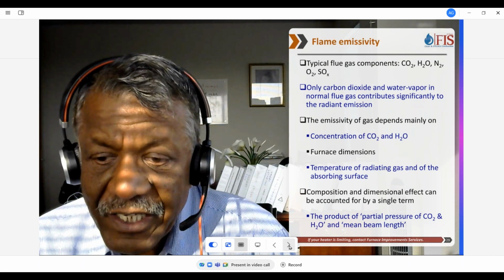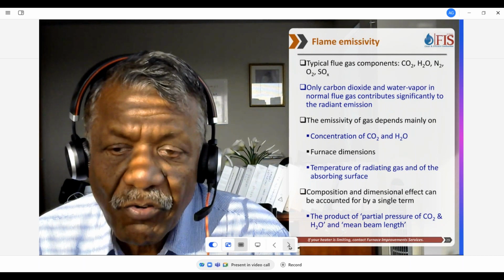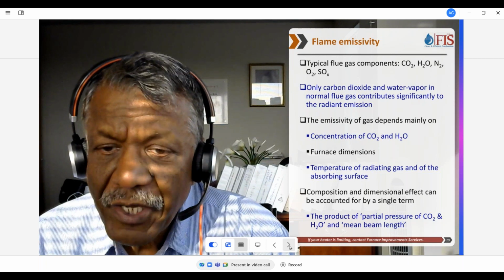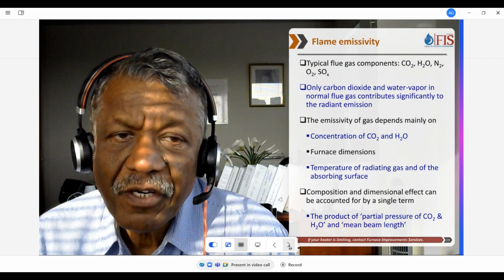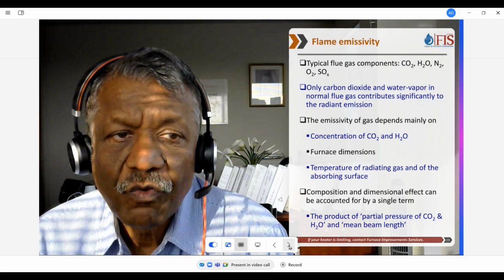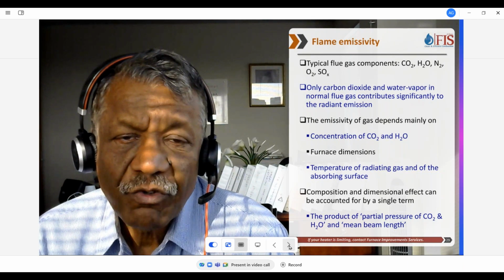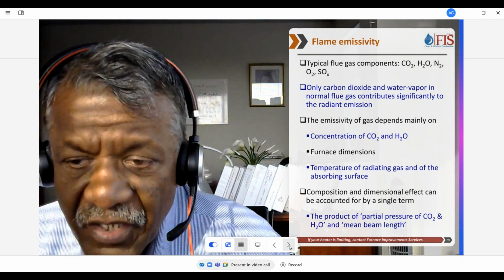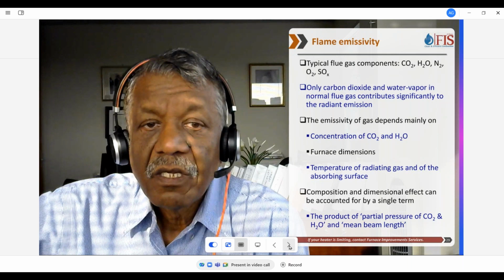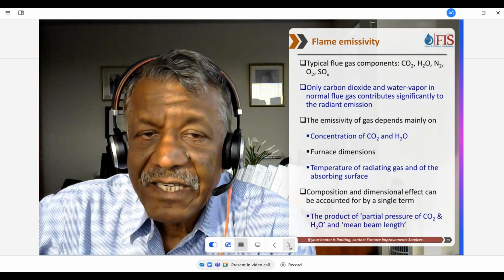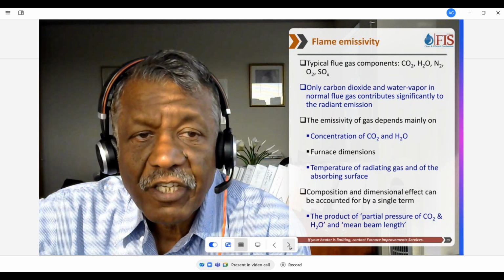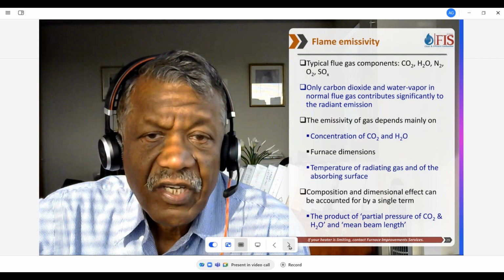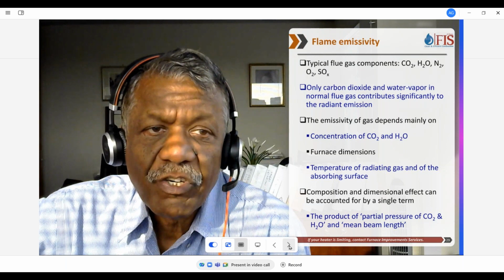And then what we start doing is we want to calculate the flame emissivity. Now, flue gases have a number of components: CO2, water vapor, nitrogen, oxygen, and SOx. And what Lobo came up with is that it is only the triatomic molecules which are radiating, like carbon dioxide and water vapor.